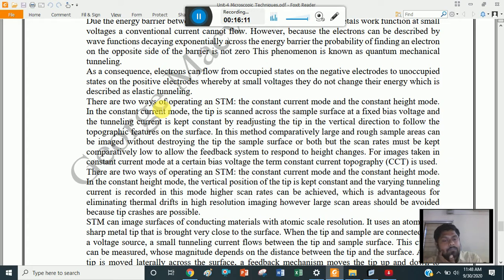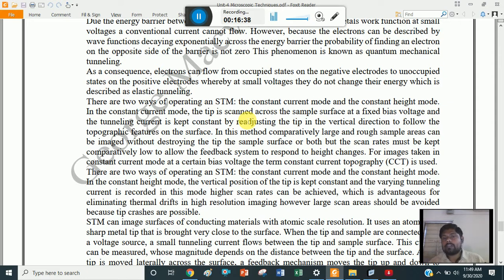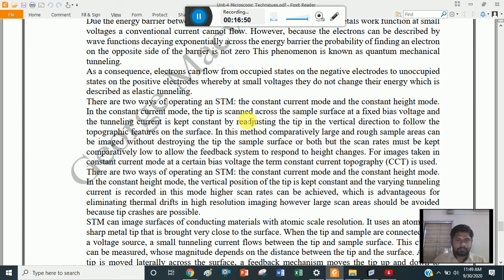There are two ways of operating STM: the constant current mode and the constant height mode. In the constant current mode, the tip is scanned across the sample surface at a fixed bias voltage and the tunneling current is kept constant by readjusting the tip in the vertical direction to follow the topographic features on the surface. Comparatively large and rough sample areas can be imaged without destroying the tip or the surface.